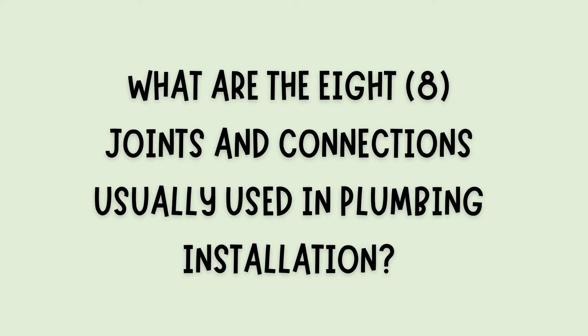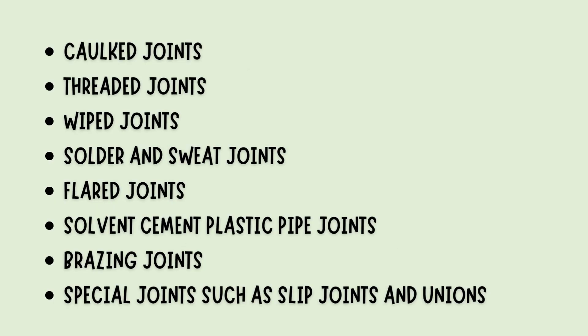That's it for our questions. Before we end our review, can you enumerate the 8 joints and connections usually used in plumbing installation? First are the caulked joints, usually used for bell and spigot cast iron pipes. Second are the threaded joints, used for iron pipe size pipe and fittings — Teflon tapes are acceptable for use on male threads only. Third are the wiped joints, used for lead pipes. Fourth are the solder and sweat joints used for copper tubings, properly fluxed by non-corrosive flux. Fifth are the flared joints used for soft copper water tubing. Sixth are the solvent cement plastic joints, usually used for PVC pipes, also called cold welding press. Seventh are the brazing joints, obtained by joining metal parts with alloys that melt at temperatures higher than 449°C but lower than the melting temperatures of the parts to be joined. Eighth are the special joints, which include slip joints for fixture drains and traps, and unions.